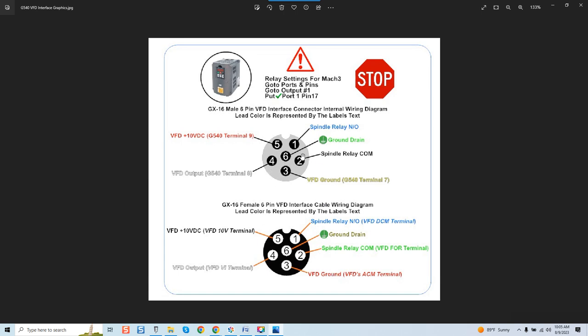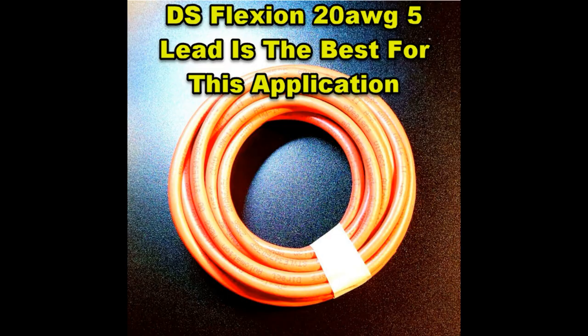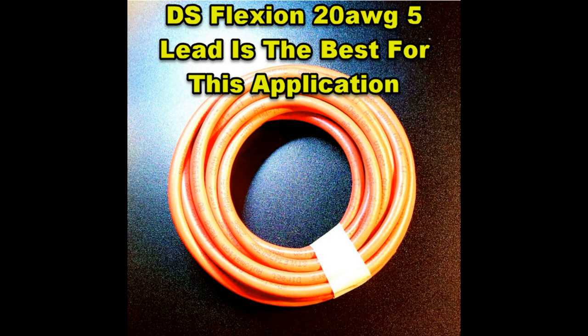Now why do I use a six pin connector? Because you can see the ground drain is allocated to terminal six. So we need that. A lot of guys seem to forget that they have a ground drain. It's an absolute must and I've said this in numerous videos that you must use double shielded cable. I recommend it highly. It's going to definitely save you a lot of headaches in the long run.